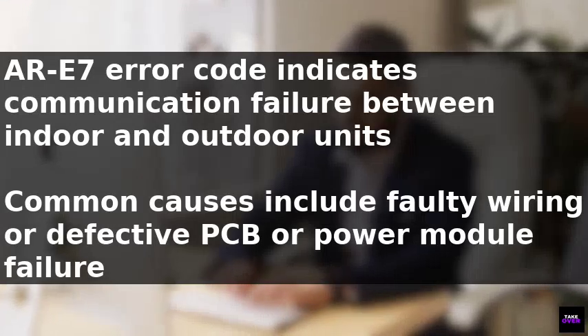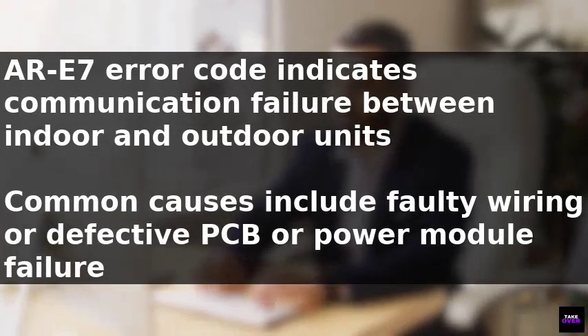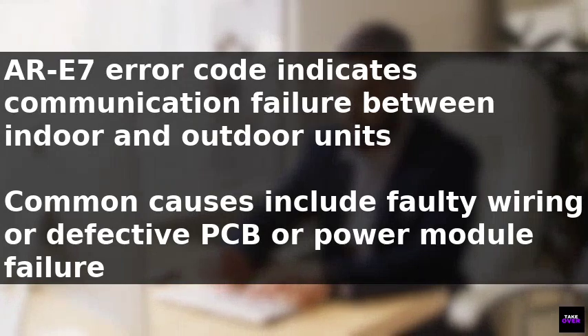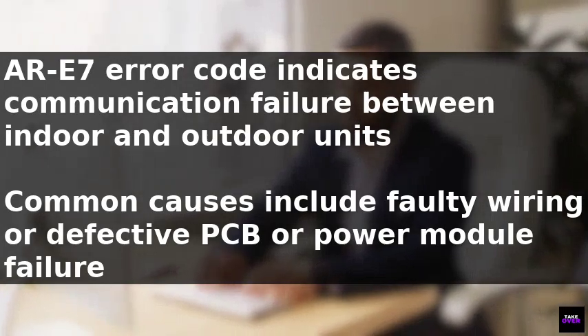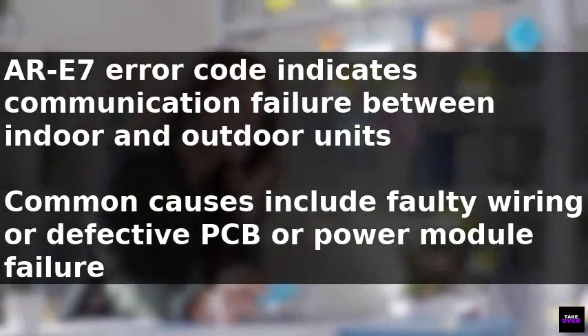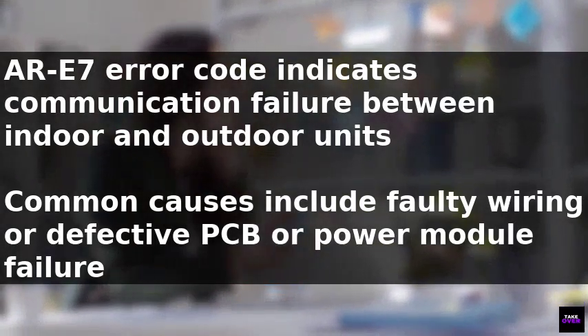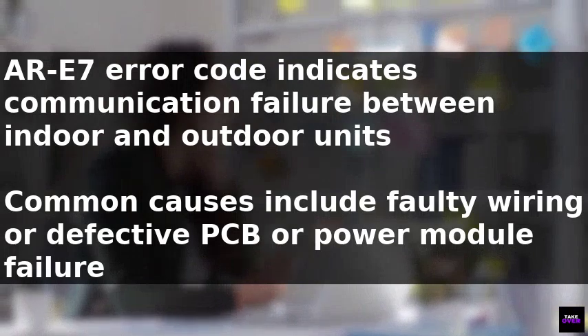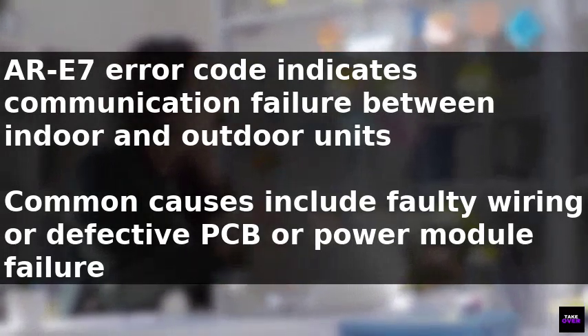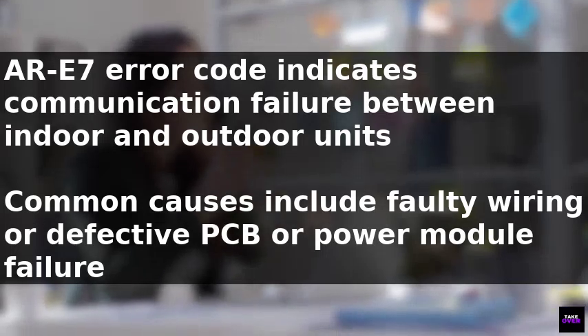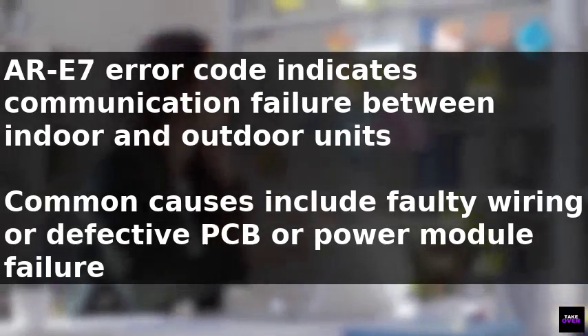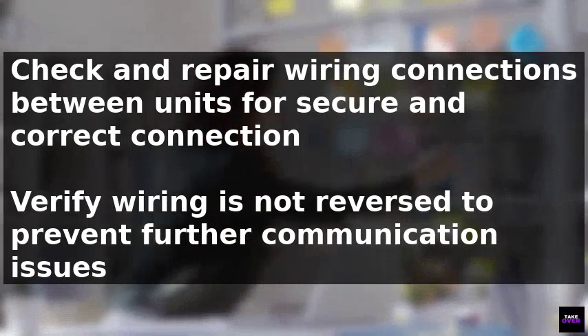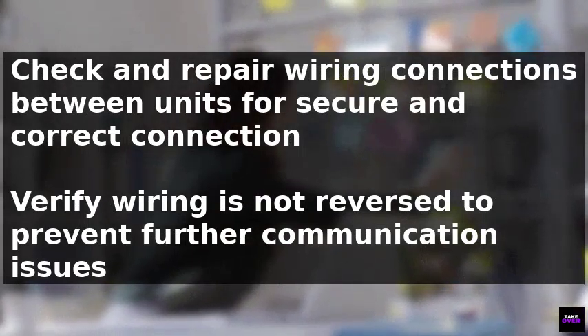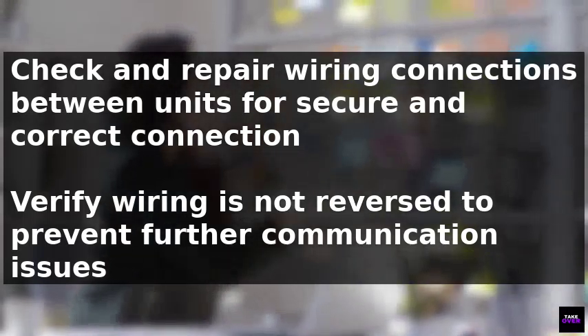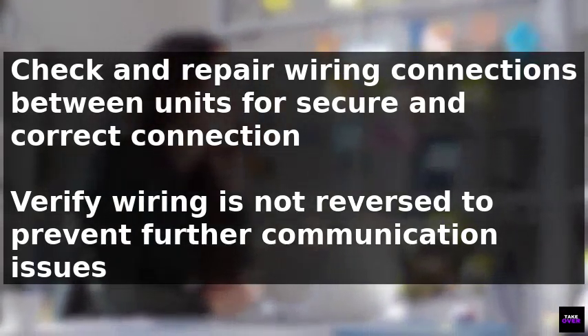To fix the ARE7 error code on a Hisense DC inverter split air conditioner, it's essential to understand what this code means. The ARE7 display indicates a communication failure between the indoor and outdoor units. Common causes of this error include faulty wiring connections between the units, a defective indoor or outdoor printed circuit board (PCB), or a power module failure.